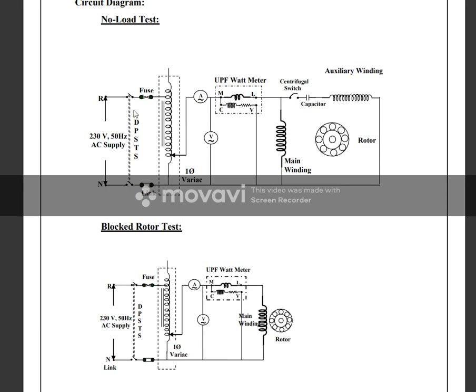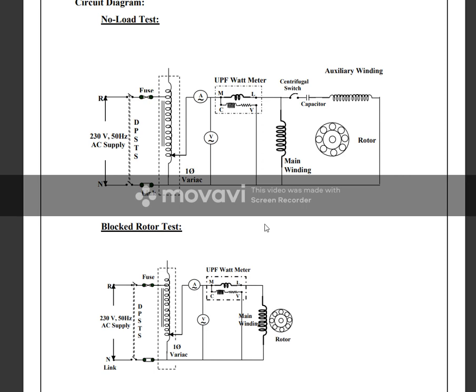We will conduct the no load test and the blocked rotor test. Connect the circuit as per the diagram, apply full voltage to 230 volts, then record current, voltage, and power. We will also do the blocked rotor test without the auxiliary winding.